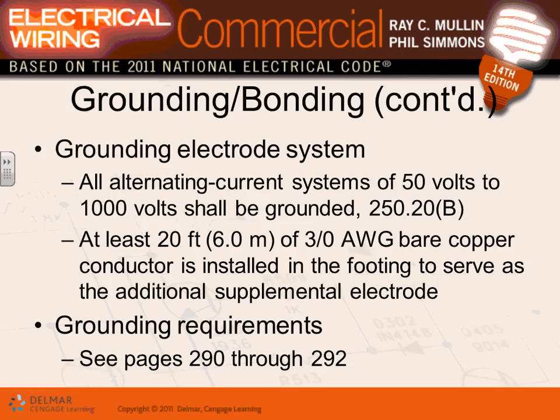All I want you to know right now is that you will take a grounding electrode conductor from the service all the way to the grounding electrode system, which happens to be the water pipe, the concrete encased electrodes, or a ground rod, and you tie that wire to it. That wire has to be continuous. It cannot be spliced. It has to be protected from physical damage. So that's basically what they're telling you. If it's connected to a rod directly, it doesn't have to be larger than number 6. So that's what all these details are about the grounding.